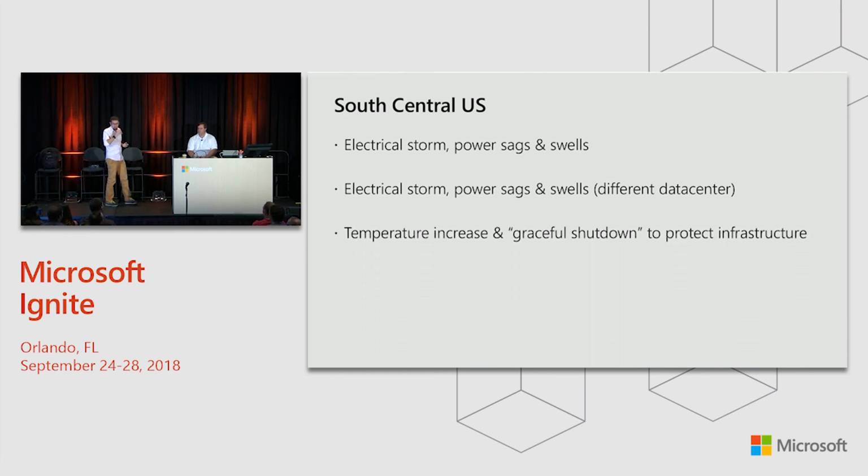After the 45-minute mark, the temperature begins to increase rapidly to a point where hardware begins to shut down to protect the integrity of itself, as designed. This is what it's supposed to do. It's supposed to shut down because it's getting too warm.